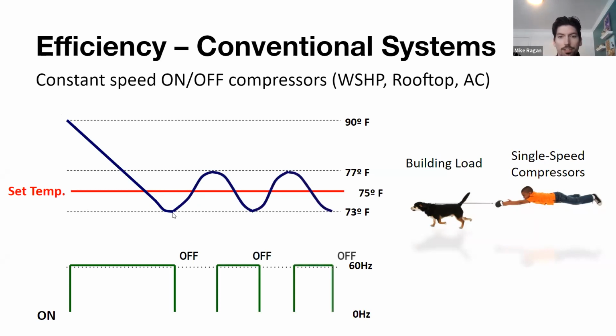It's going to overshoot a little, down to 73. We're going to turn that off, and the temperature in the space is going to rise all the way up again, up to 77. It's going to turn back on, and we're going to have a pretty wide range that we're actually going to be feeling in that interior space, from 73 to 77 degrees. Now, that's ultimately why I'm saying you're letting the dog walk you on this walk, as opposed to being in control of the situation. I'm going to contrast that now with a variable speed compressor.